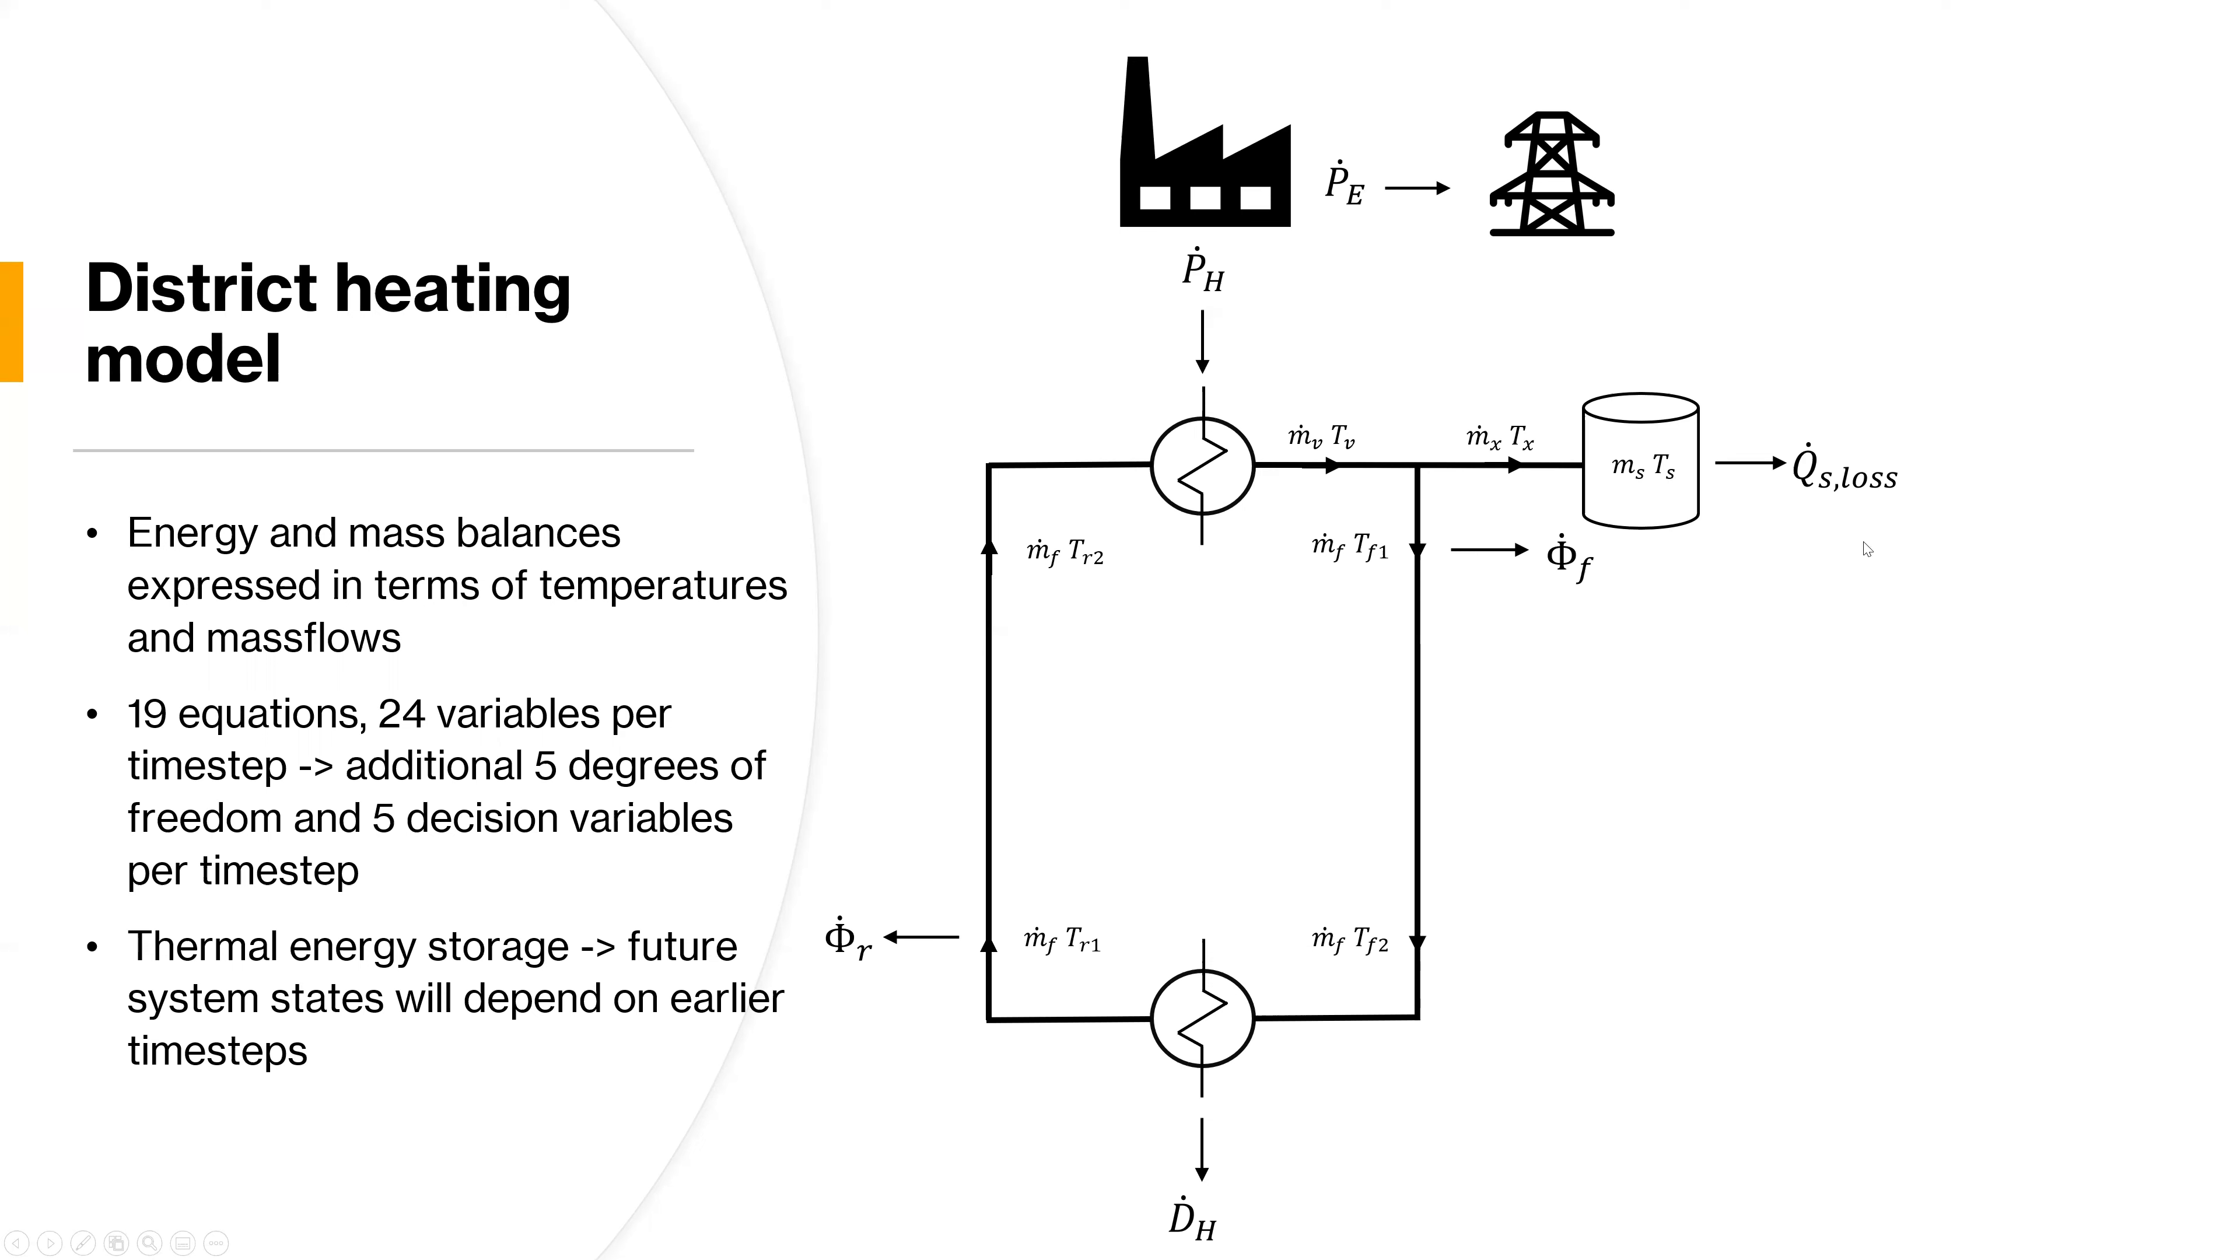And it has a thermal storage, as you can see over here where the energy contained is defined also in terms of mass and temperature. Then we have included different heat losses in the system, we have a storage heat loss, a forward transmission heat loss and a return transmission heat loss. Then we have the demand node down here, which is basically an aggregated node for all the distribution network. We end up with 19 equations, 24 variables per time step, which gives us five decisions in total, or five additional decision variables per time step that we are implementing this model.